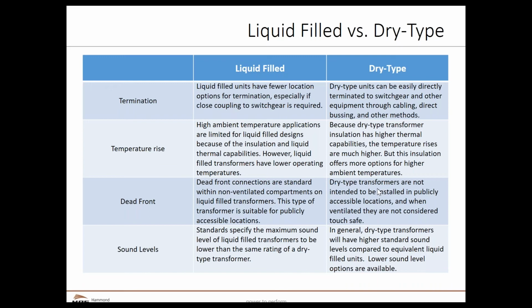Sound levels, again, liquid filled will be a little bit quieter than dry type by the very nature that the core coil is submerged in the liquid, and that helps deaden the sound. You can do lower audible noise transformers with dry type, but they tend to cost a little bit more and be a little bit bigger. However, because liquid filled transformers don't have all of the temperature rise options that dry type do, oftentimes with liquid filled, it might be more common to employ cooling fans, which can greatly increase the dB level of that particular transformer.